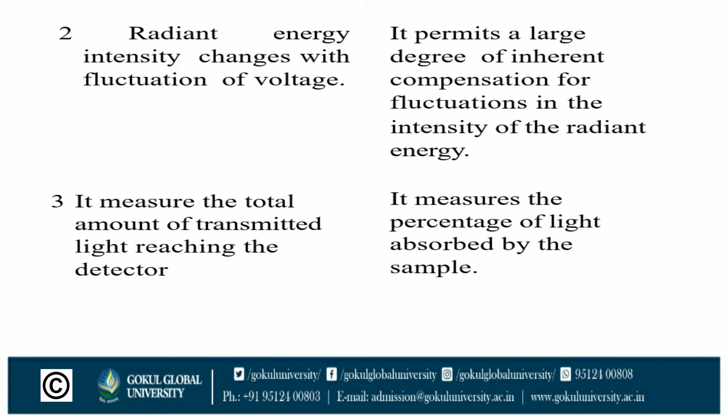Third: in the single beam, radiant energy intensity changes with voltage fluctuation. In the double beam, it permits a large degree of inherent compensation for fluctuations in the intensity of the radiant energy.